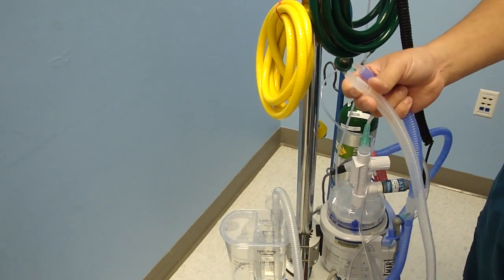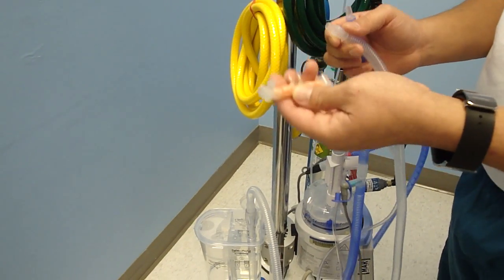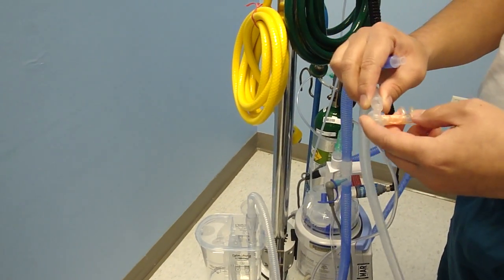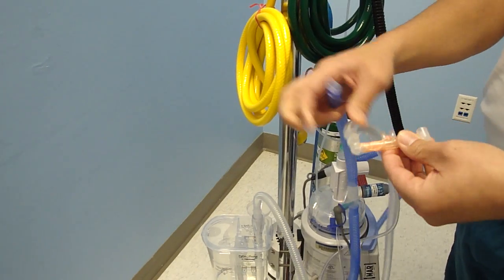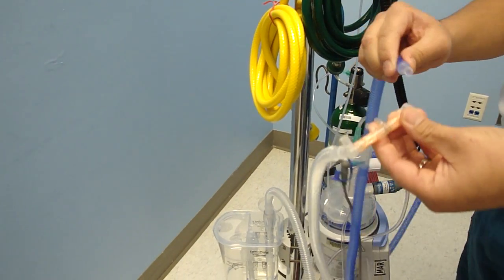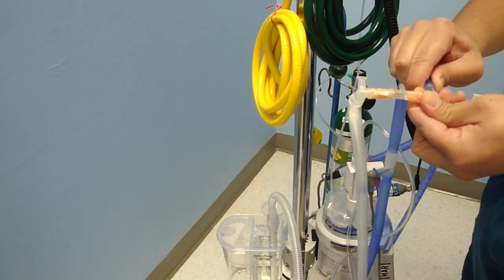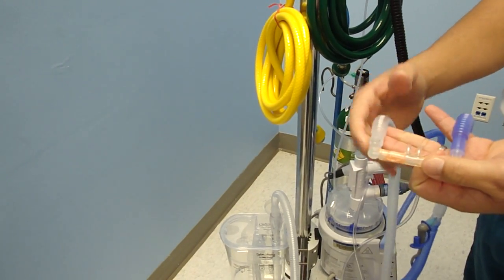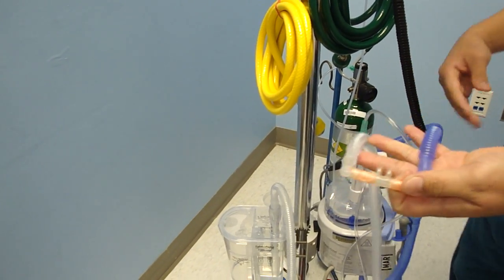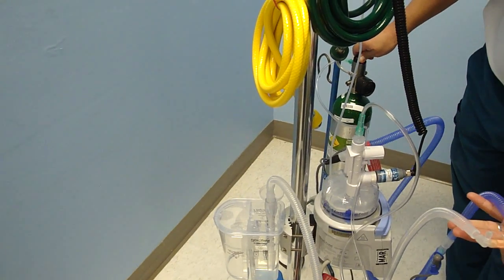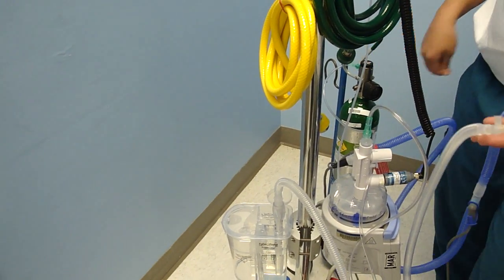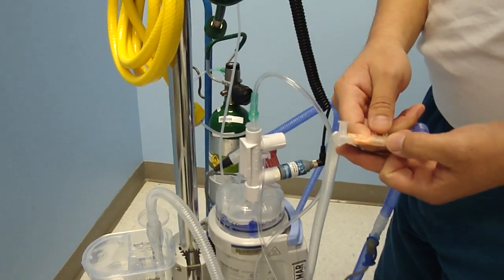Okay, then you will have your Hudson prong, is what we use, and it should fit direct to the Hudson prong. You don't need any special adapter, and no more temperature probe sticking out to the baby. Okay, let's turn it up to 8 liters. That's the common flow meter setting that we use. I'm going to pinch the prong to make it bubble.